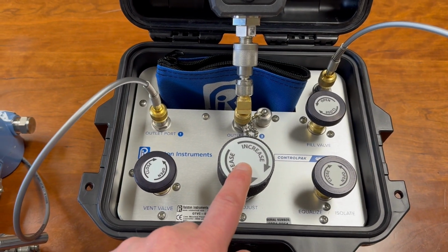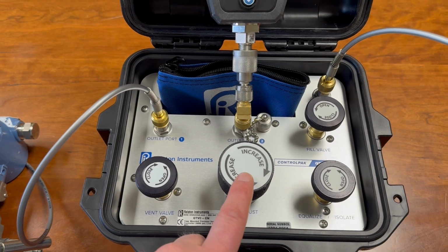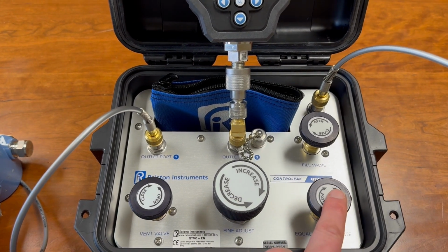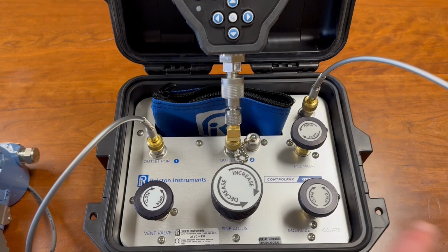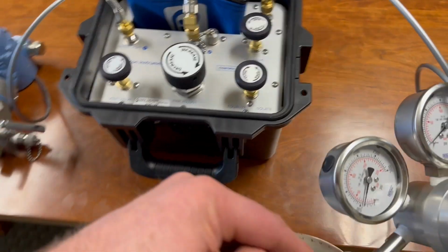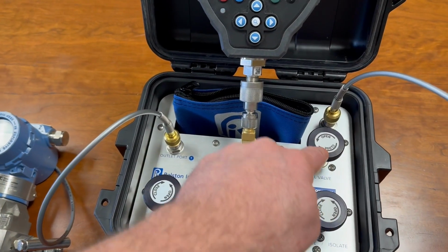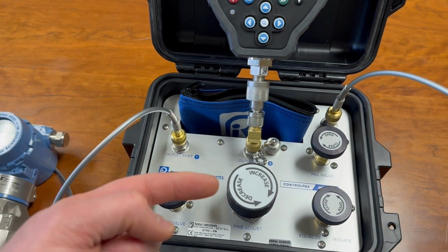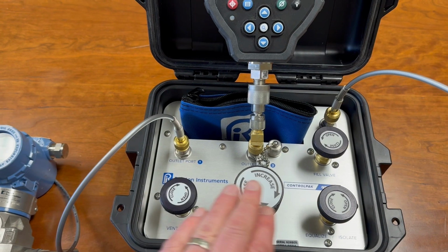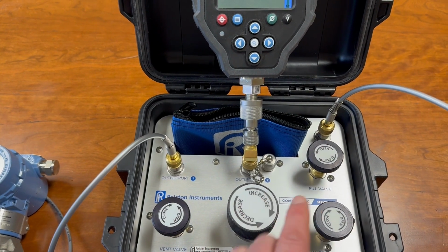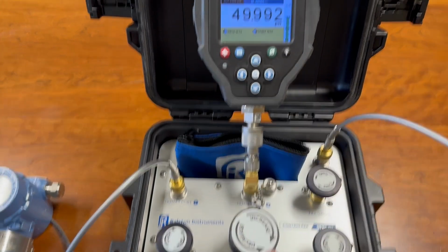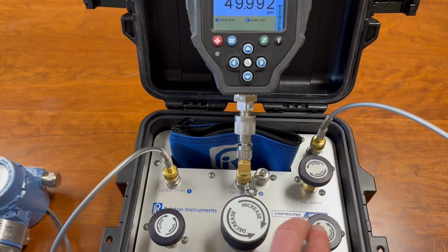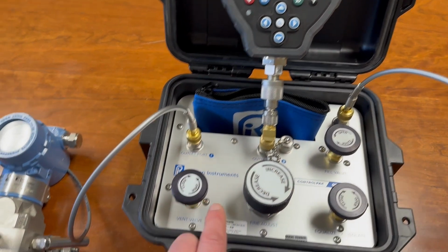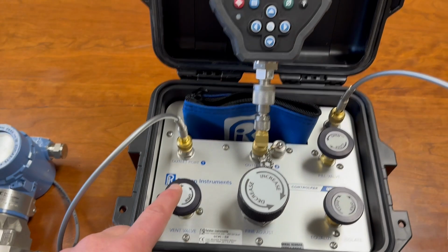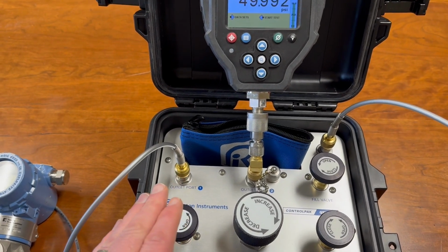It was that quick. Now the next thing we want to do when we go to the next test point is open the equalize isolate valve, increase the pressure on the regulator, open this fill valve and bring that pressure back up, and then repeat that. So when we have completed all the upscale pressure points in the test, and we want to do downscale pressure points, you can simply reverse the process, but then you're using the vent valve, and you would vent the pressure down between test points.